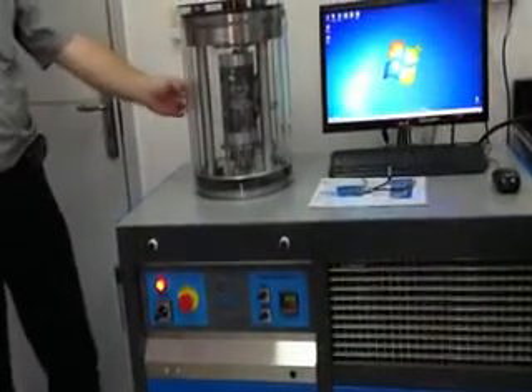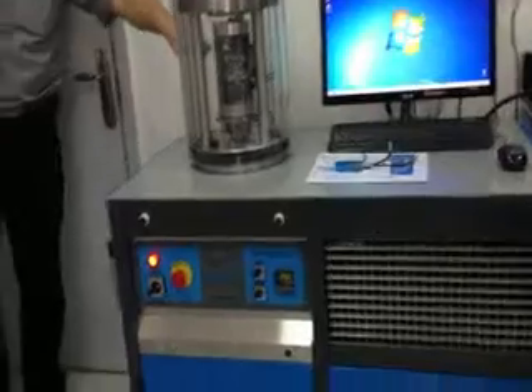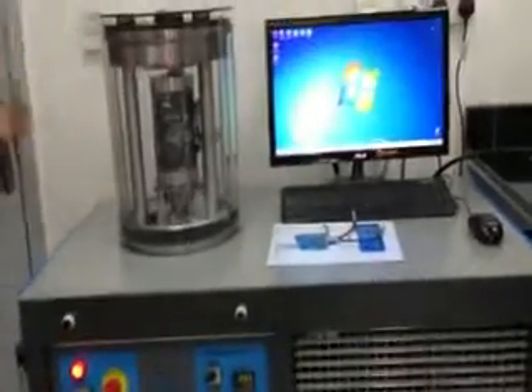If you look inside the chamber, you'll see there's a temperature probe behind the sample. So maybe come around and have a look. Do you see the temperature probe? Yes, this line behind the steel rod. So from there you can read the temperature, on the sensor and the software, and also on the controller.